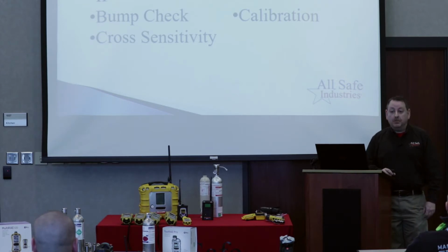You know, we calibrate the LEL sensor to methane, but it might not always be a methane response that you're on. You might be responding to something that involves hydrogen or acetylene. So the LEL sensor responds to a wide variety of flammable vapors, and correction factors will actually help you dial in to get a more precise reading. And so I'm going to show you how to set correction factors so everybody's comfortable with that as well.